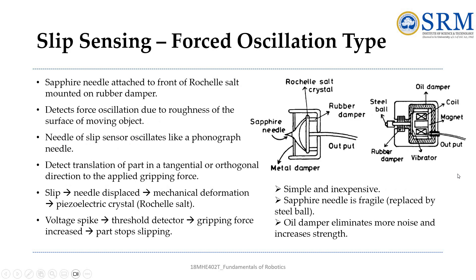The next type is the forced oscillation slip sensor. Imagine a sapphire needle attached to the front of the device — sensitive to touch like a phonograph needle on a record player — that can feel any roughness on the surface of an object it's holding. When the object starts to slide, the needle moves, causing a mechanical change in a special crystal called Rochelle salt. This change results in a sudden increase in voltage which acts like an alert signal, triggering a mechanism to increase the gripping force and stop the object from slipping.